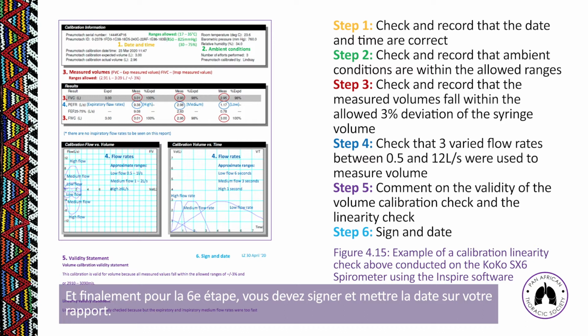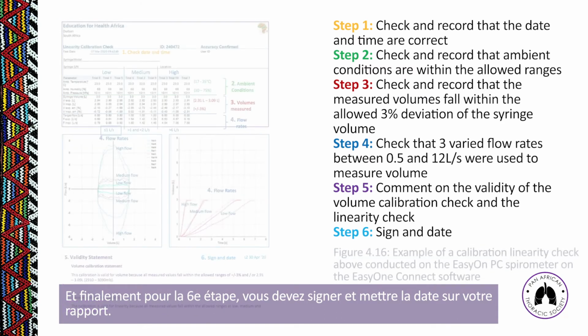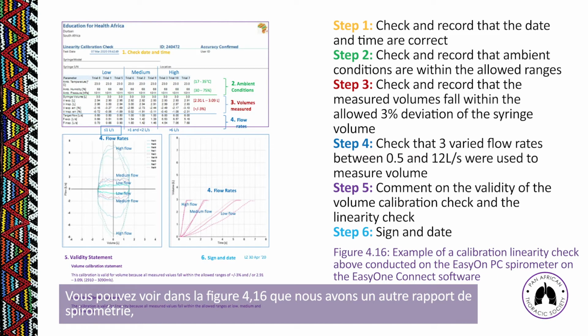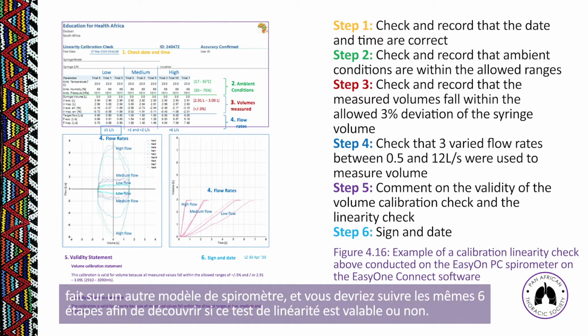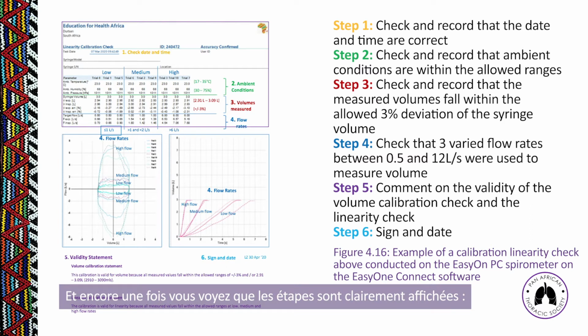And then lastly, step number 6, you need to sign and date your report. You can see that in figure 4.16, there's another calibration report done on a different spirometer, and you should follow the exact same 6 steps to find out if this is a valid linearity check. And you can see again that they are very clearly labeled. Yellow, step number 1, check your date and time. Step number 2, check your ambient conditions at the time of calibration.